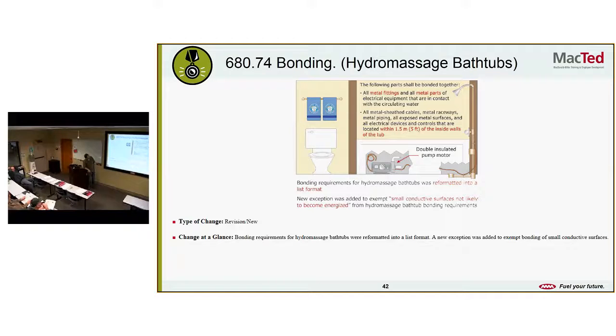All metal fittings and all metal parts of electrical equipment that are in contact with the circulating water. All metal sheathed cables, raceways, piping. Well, they exempt, probably like, so apparently there was a requirement to bond all small metal surfaces within a shower enclosure. So maybe like a washcloth holder. Now they're saying that'd be kind of dumb to have to bond that. So they made an exemption for that.